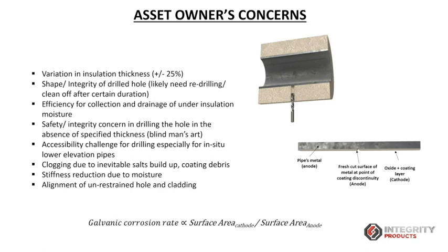Another challenge with the drill hole is that the moisture coming out through the drain hole or the drain plug is not clean water. It's not pure water. It contains dissolved gases, suspended solids, maybe damaged coating. It contains a lot of things, and it can potentially clog the drain hole. So we need a system to clean it up frequently.